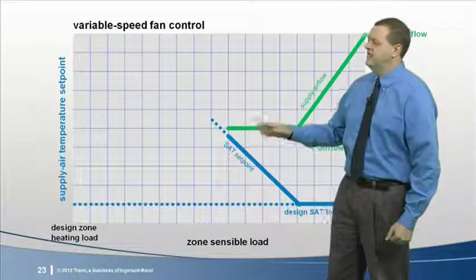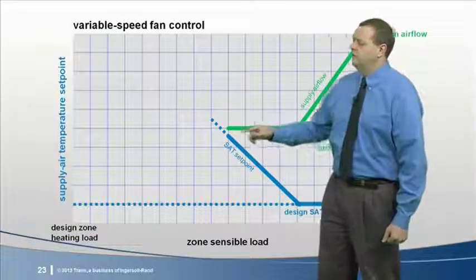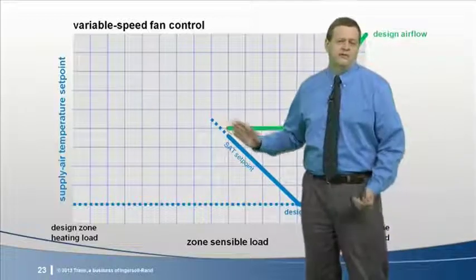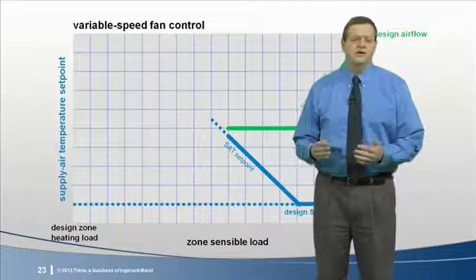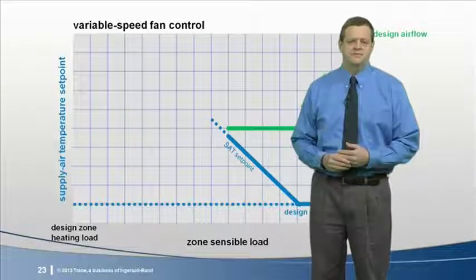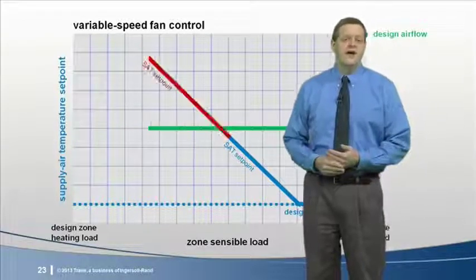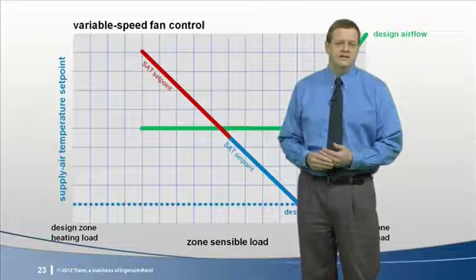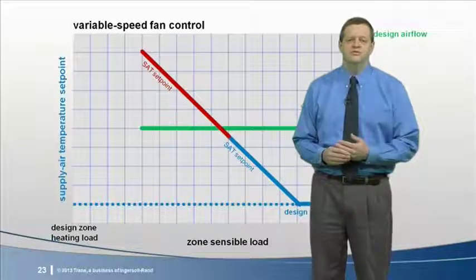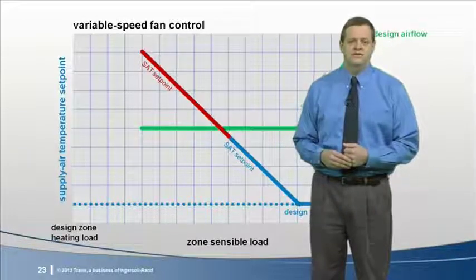Here the fan continues to operate at this minimum airflow with no compressors or heaters operating, and the zone temperature is just allowed to float within that dead band. Now let's consider what happens when the zone eventually requires heating. That is, when the zone temperature drops to its heating set point.